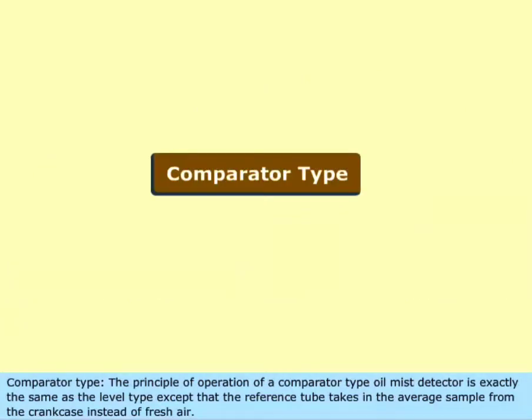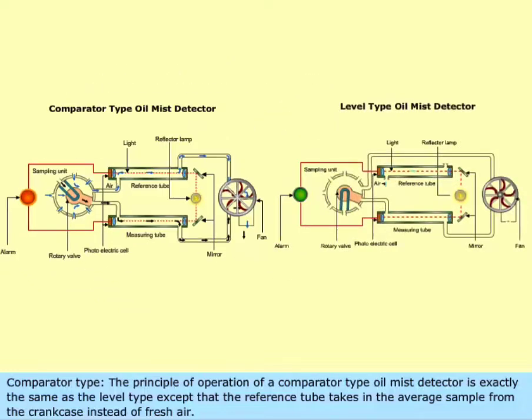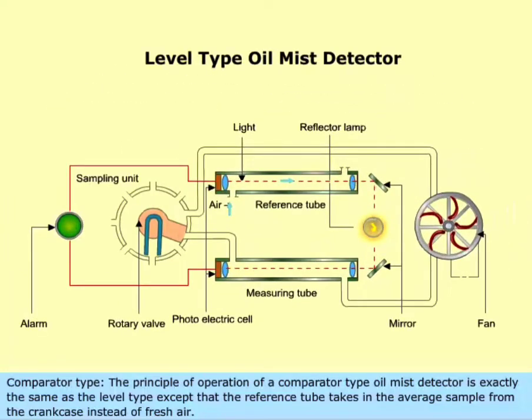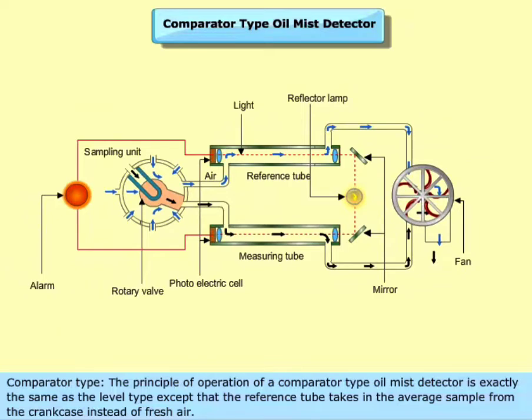Comparator Type. The principle of operation of a comparator type oil mist detector is exactly the same as the level type, except that the reference tube takes in the average sample from the crankcase instead of fresh air.